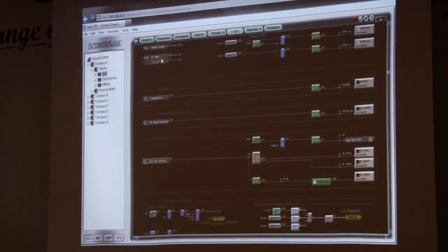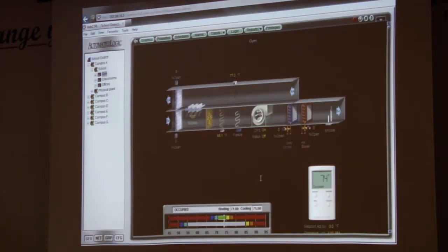All right, gone. And I can come back to my graphic and I can see in a minute I'm going to see my status. There we go. So now my fan is getting status. Based on my discharge air temperature and my set points, now my program is proving flow. Then my valves are going to start to open to maintain my temperature. So this was a way to utilize a lock as a fix for now, a Band-Aid, if you will, while you're dealing with the problem, okay?